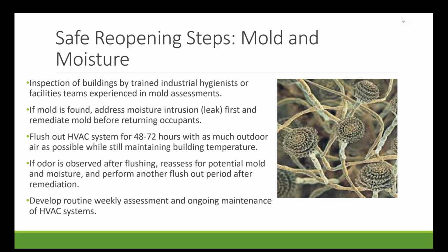After any necessary remediation, or if nothing looks or smells suspicious, you would do a flush out of the HVAC system for 2 to 3 days with as much outdoor air as possible while maintaining building temperature. After this flush, you'd go back in and check for any odor or anything missed from the original remediation. If you notice anything, reassess, look again for mold and moisture, and perform one more flush out after that level of remediation. Once you're back in the building, do a weekly assessment and ongoing HVAC maintenance to prevent mold from developing.